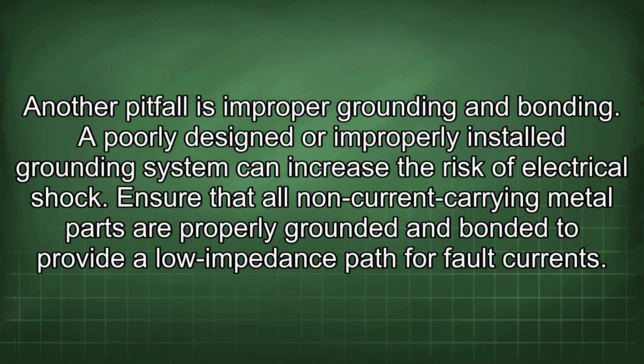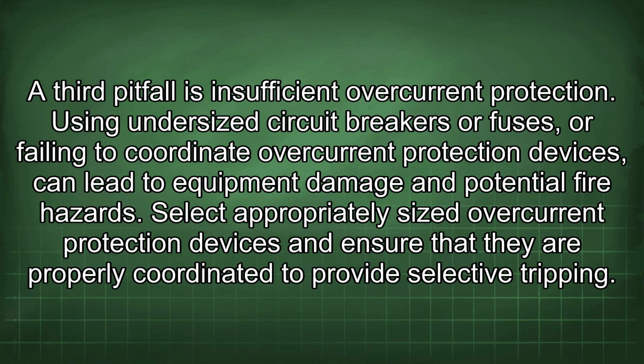Ensure that all non-current carrying metal parts are properly grounded and bonded to provide a low impedance path for fault currents. A third pitfall is insufficient overcurrent protection. Using undersized circuit breakers or fuses, or failing to coordinate overcurrent protection devices can lead to equipment damage and potential fire hazards. Select appropriately sized overcurrent protection devices and ensure that they are properly coordinated to provide selective tripping.